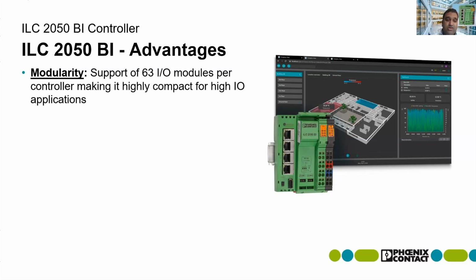What's good with the ILC controller is it complements what data center operators want to see, which is modularity and being able to build in more building-block kind of design. The controller supports up to 63 IO modules per controller, offering the operator or system integrator the ability to design a high IO compact application. To put it in perspective, one digital input card can support up to 32 input points - times that by 63 and you can see how high the count can go. Being more modular also makes it more scalable in its design.